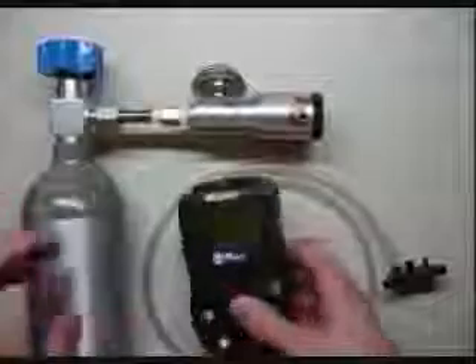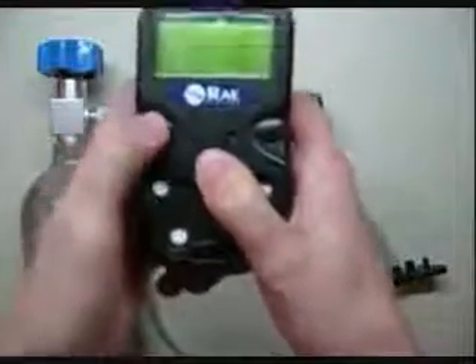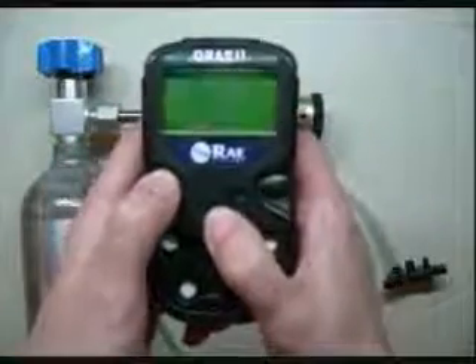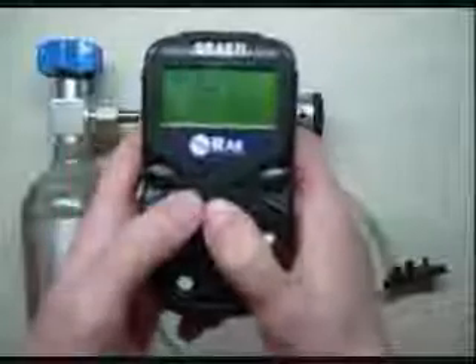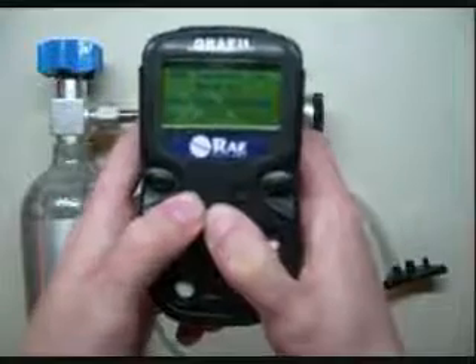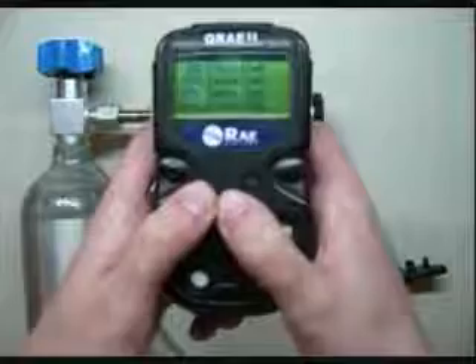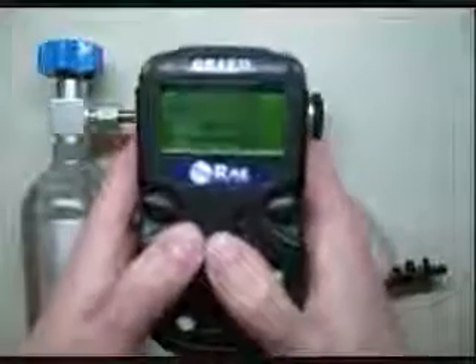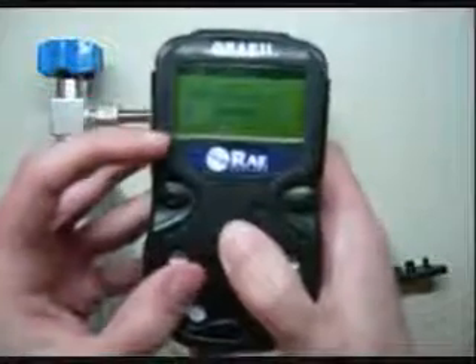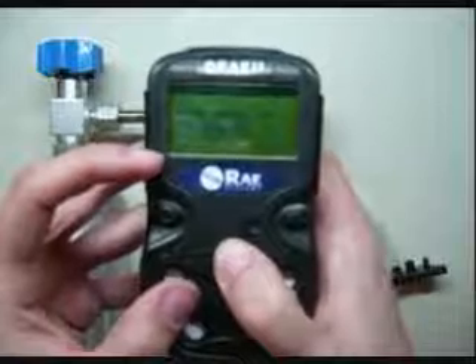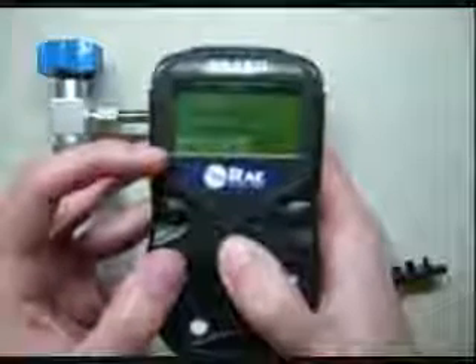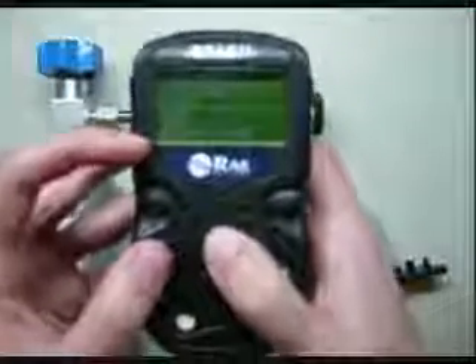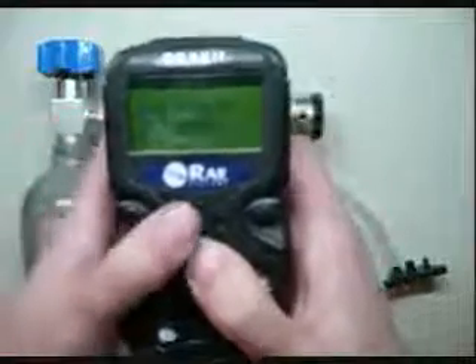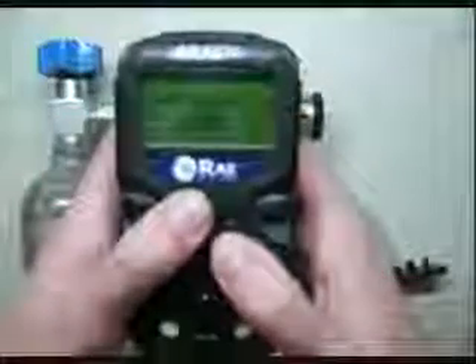Start off by taking the monitor and pressing the button on the left, holding it down until the unit beeps and it says on. Go ahead and release it, and it'll go through a startup check. I'm going to apologize if it's a little difficult to see on this camera. Here it says all the sensors are installed, and it goes through a warm-up period of 15 seconds. Usually before you calibrate a unit, you should give it a little bit longer than that if you could. Try and give it 5 minutes or so to get everything warmed up in there.